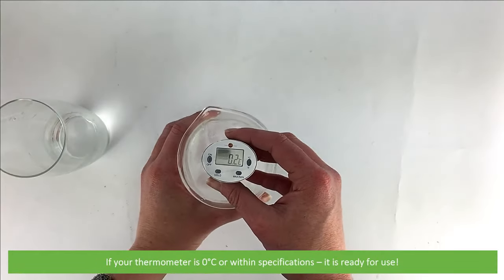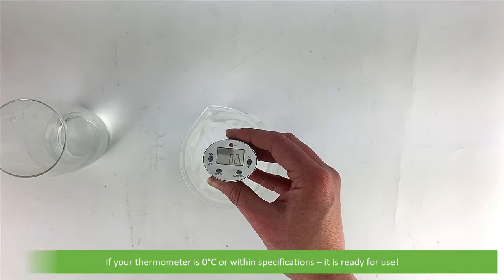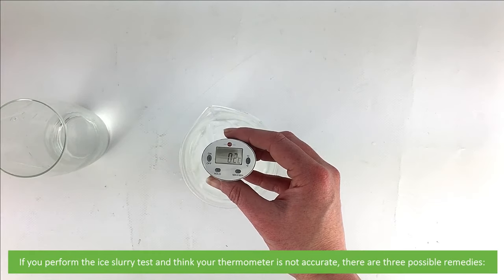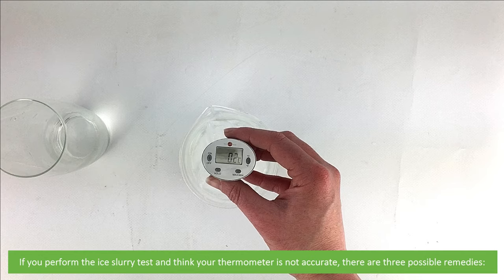If your thermometer is zero or within its specifications, it's ready for use. If you have performed this ice slurry test and you think your thermometer is not accurate, there are three possible remedies.